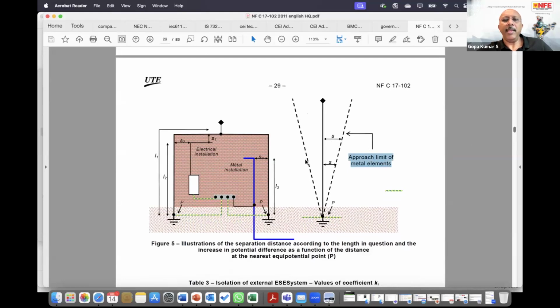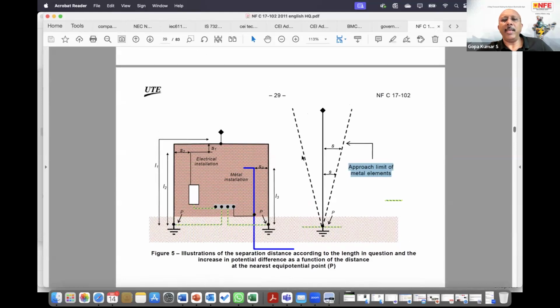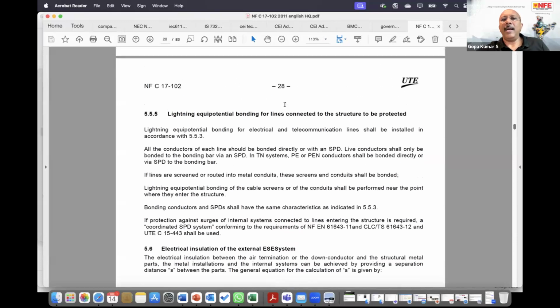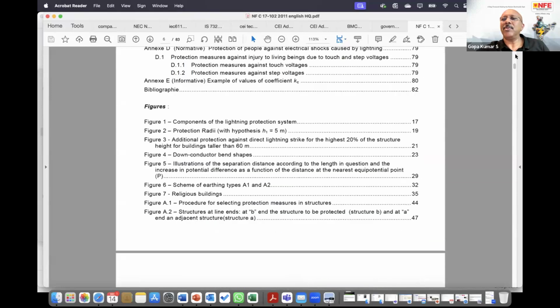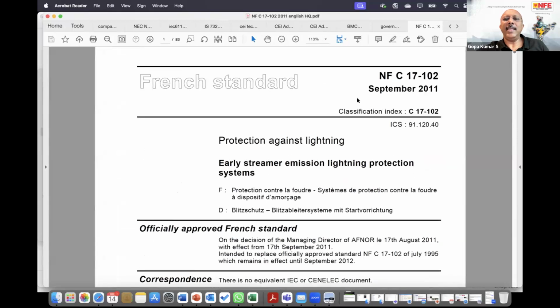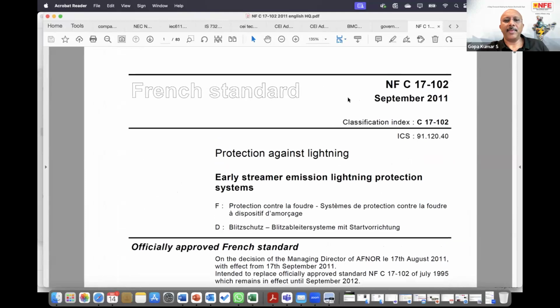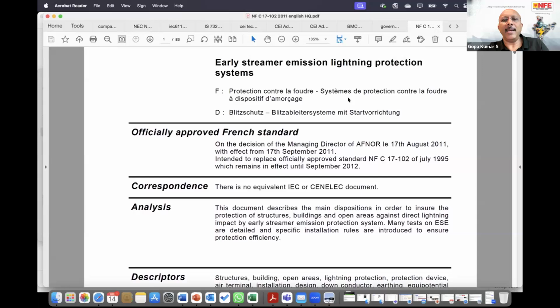Now to conclude, if you put an ESE rod in a building of, let's say, 10 floors with one down conductor and one earth electrode, technically, if you read the NFC standard, you have to keep it 2 meters away from the building, away from the entire structure of the building. So basically, I would say NFC 17102 is a very intelligently made product standard, and the Europeans know how to apply it and they don't violate the rules, whereas the manufacturers come with this particular standard in India and educate the whole market saying that one rod, one down conductor and one earth pit, the entire area is protected, which is absolutely nonsense as per this standard itself.